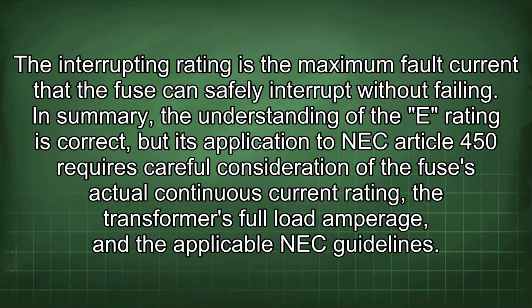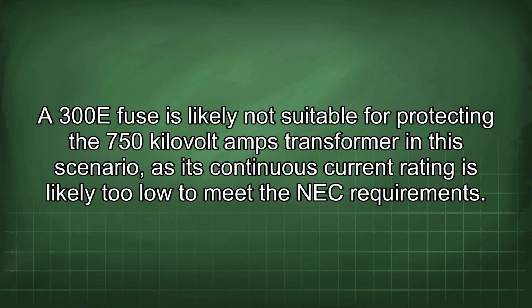In summary, the understanding of the E rating is correct, but its application to NEC Article 450 requires careful consideration of the fuse's actual continuous current rating, the transformer's full load amperage, and the applicable NEC guidelines. A 300E fuse is likely not suitable for protecting the 750 kVA transformer in this scenario, as its continuous current rating is likely too low to meet the NEC requirements.